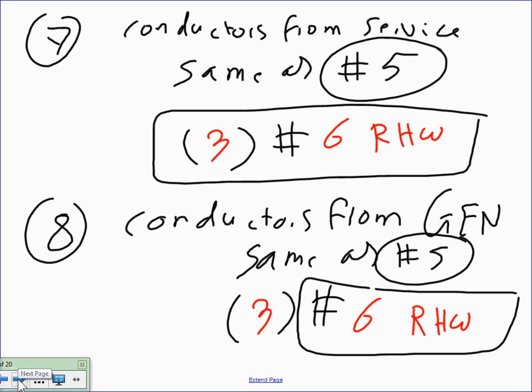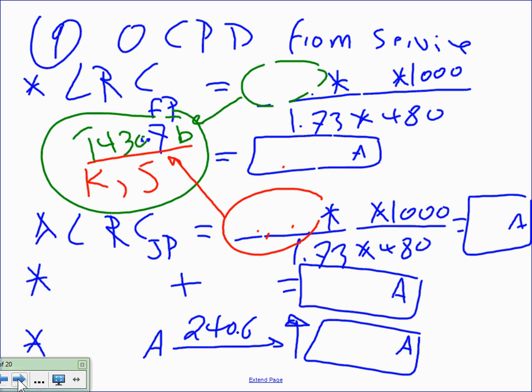are identical. No gimmicks, nothing. Now number 9, if you go to number 9, this is the overcurrent protection device that's coming out of the line side of the service disconnect means. If you look at the picture in front of you, by code you have to feed the fire pump from the line side of the service disconnect means. And you have to have an overcurrent protection device for it. And that overcurrent protection device has to be big, fat, and fluffy to handle the locked rotor current.